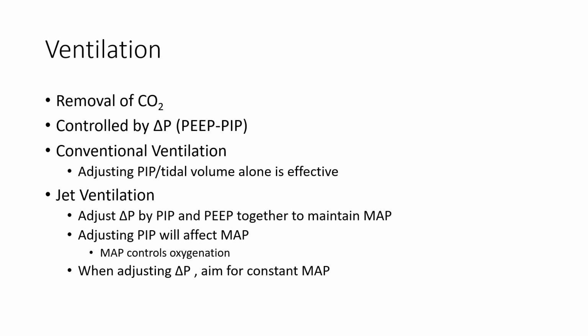The tidal volume delivered by the jet ventilator is typically smaller and delivered faster than high-frequency oscillatory ventilation. Ventilation is the transport of carbon dioxide through the respiratory system. The jet is extremely efficient in removing carbon dioxide from the lungs, and small adjustments can result in major changes. The jet ventilator controls ventilation through the difference of the PIP and PEEP, or delta P.